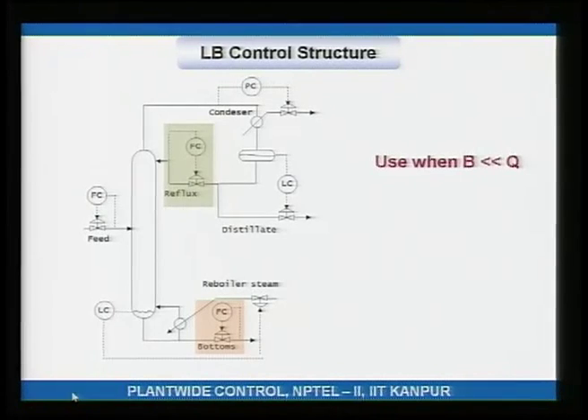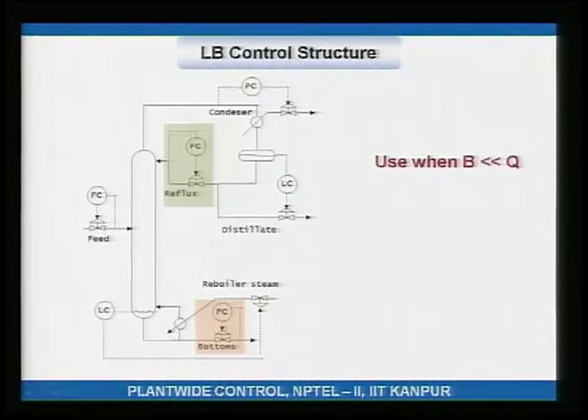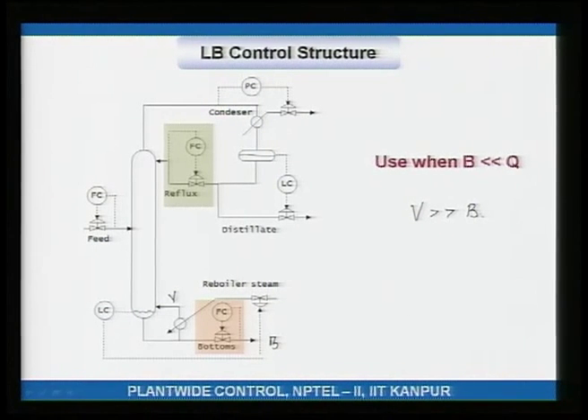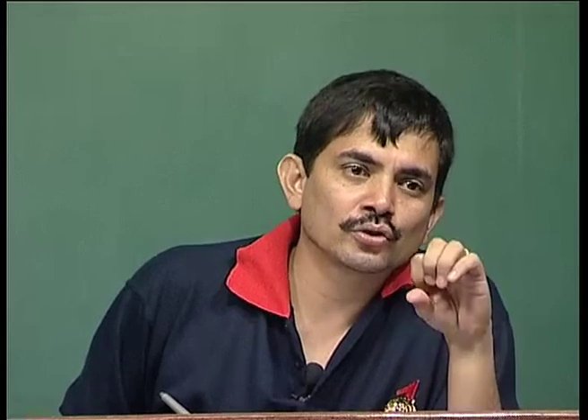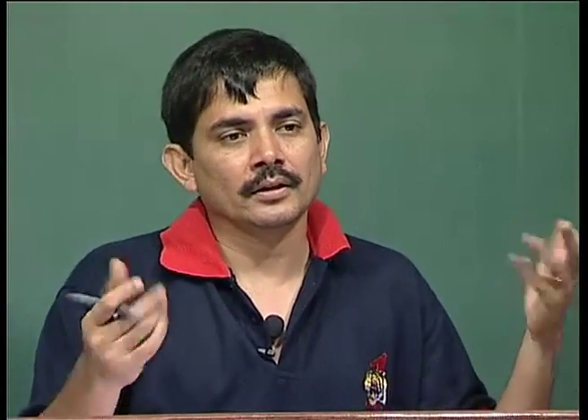The LB control structure has the reflux drum level controlled by the distillate flow rate. At the bottom, the bottoms stream flow rate is very small compared to the reboil V, meaning V is much greater than B. With respect to the reboiler, the bottoms stream is like a leak, and you cannot expect a leak to regulate a level.